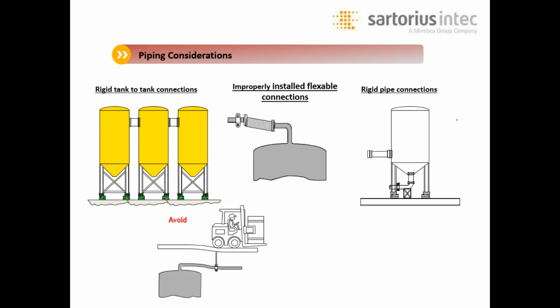Avoid hanging it from a floor where the floor may vibrate above, like a mezzanine where you have piping attached to that, where either equipment or people could walk across and cause an introduction of weight changes in the vessel contained below. There's an example of a perfect one. In a perfect world, this would be how we'd set it up. Shoulder-mounted tank sticking through the floor with long horizontal runs from the tank and the piping.